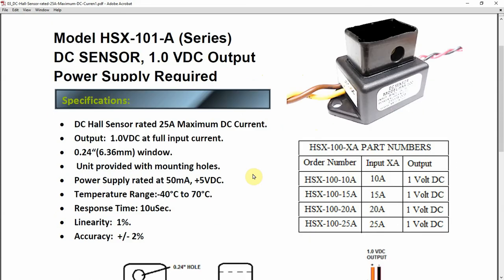The sensor's operating temperature range is -40 Celsius to +70 Celsius, and it comes in a variety of input ranges from 10 amps to 25 amps. Qualitrol provides a standard 20 amp range sensor which is suitable for most of the applications. The sensor also has a response time of 10 microseconds, making it one of the fastest sensors for breaker monitoring. It offers 1% linearity and ±2% accuracy.